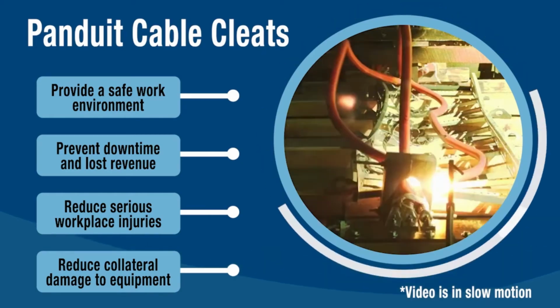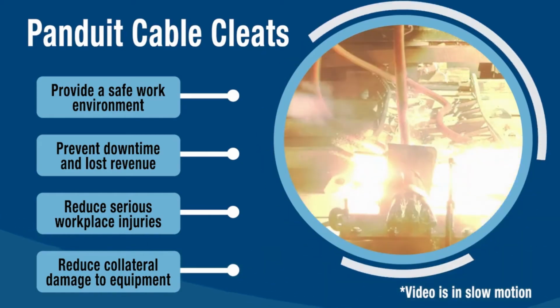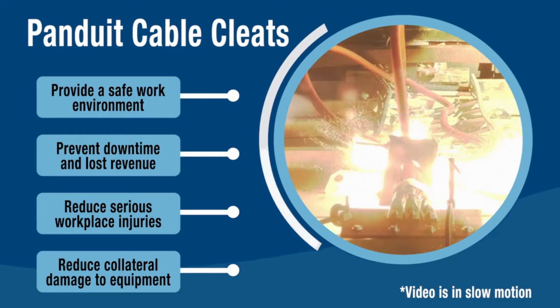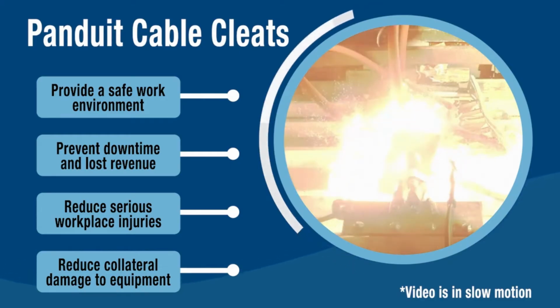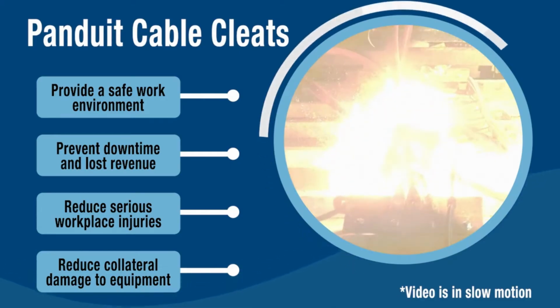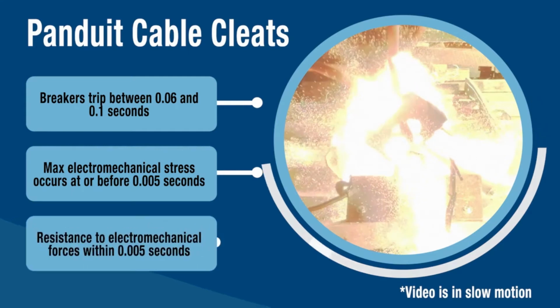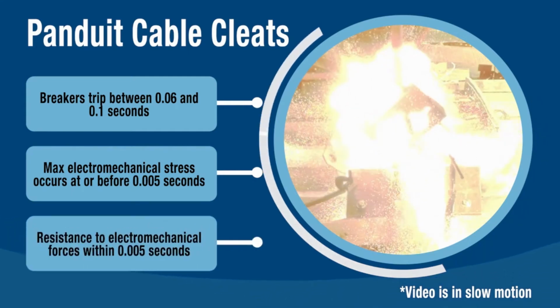Typical circuit breakers trip and interrupt a fault between 0.06 and 1/10 of a second. During a short circuit fault, the maximum electromechanical stress between conductors occurs at around 0.005 of a second. Cable cleats are resistant devices that provide resistance to those electromechanical forces before a circuit breaker trips.